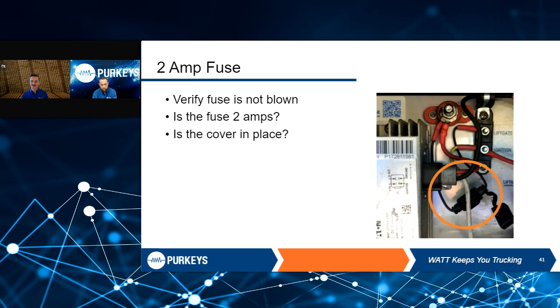Looks like it's missing a fuse there, but more importantly, even if there was a fuse, if you follow that circuit, it's missing the connection at that terminal block up there, that orange wire that goes through the 4-connector harness up to the liftgate system, the charging system at the front. So keep an eye on that.